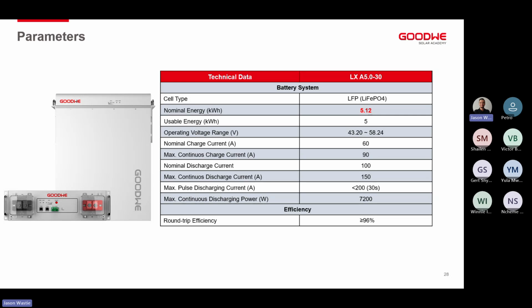So where that can come into play is if we've got a 6 kilowatt inverter, we can connect it to one battery. Obviously not going to be for a long duration of savings or long duration of backup. However, we can do it this way if they have short backup times that they require before they run the generator or whatever it is, or secondary AC output, or however we want to run this, we can just use one battery and be able to get up to 7.2 kilowatts of discharge.